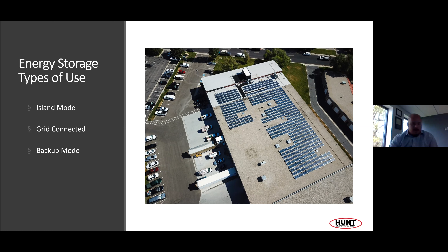The third one is backup mode. This is like using a commercial battery in your building as a giant uninterruptible power supply, or UPS — similar to how people have a battery pack attached to their desktop computer. If the power goes out, the computer stays operational, but only for a limited time. With backup mode, we look at whether you have a critical load in your house or building that requires that constant power during a utility outage, generally for a reduced time window rather than full functionality.